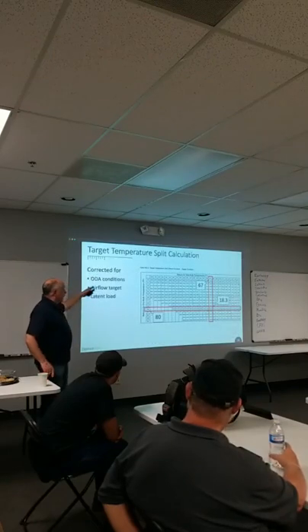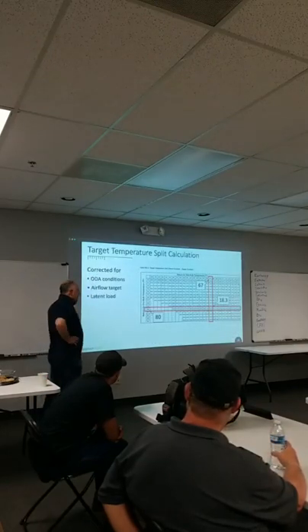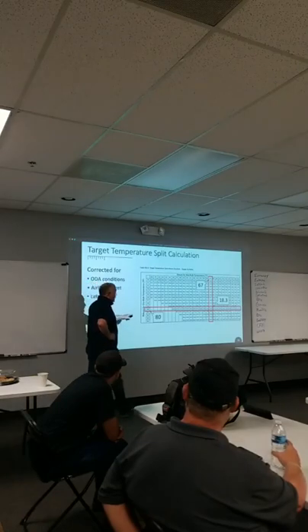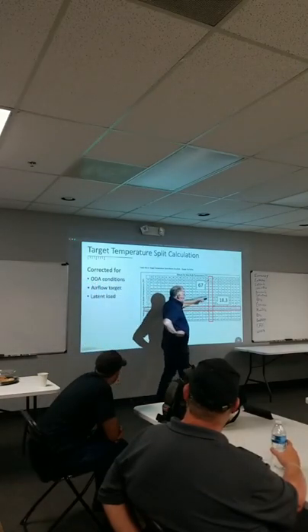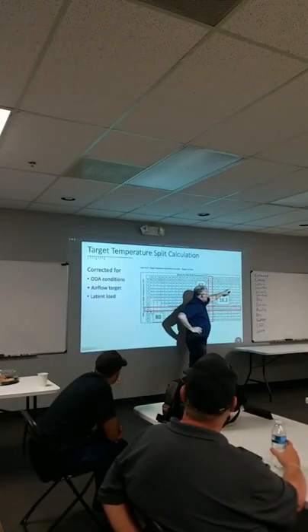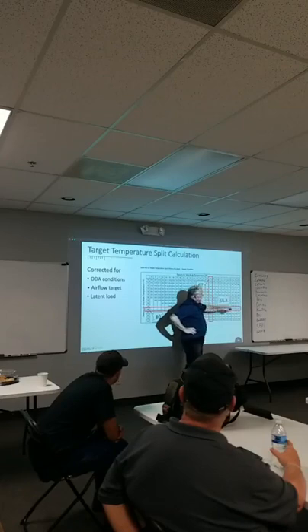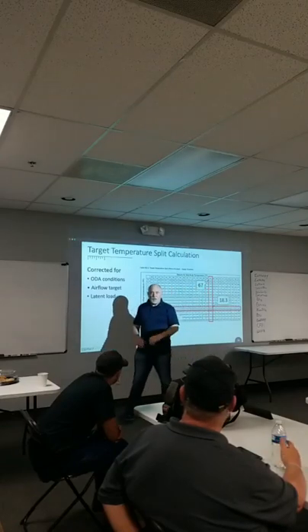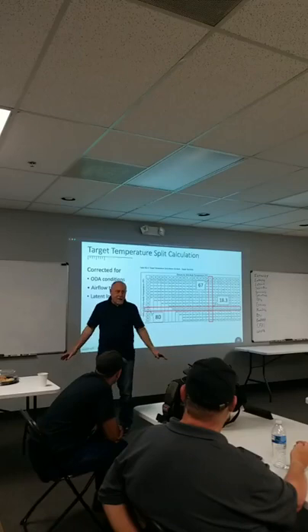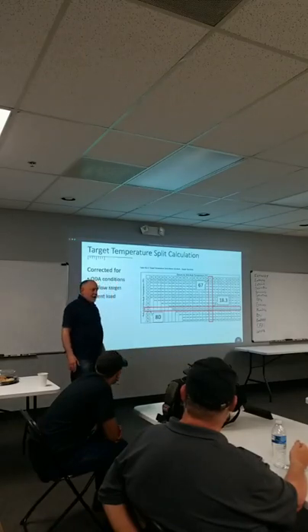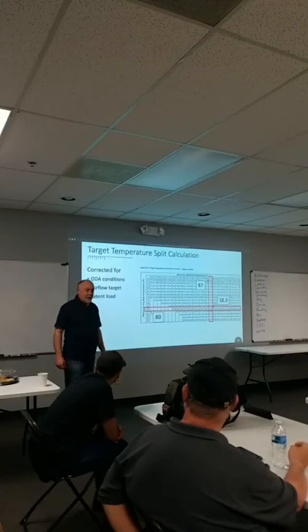Another one is our target temperature split calculation. This one's an interesting one because a lot of guys don't know this. You could start up a piece of equipment on a job site and you could have a split at 9.6 degrees and it'd be totally fine, right? You walk in there and you go, oh my God, I got a 9-degree split. What are most guys doing? Add charge. Slowing the fan down or adding charge.